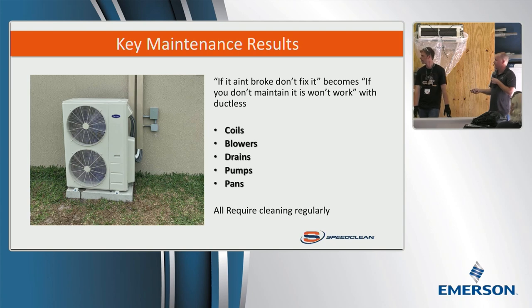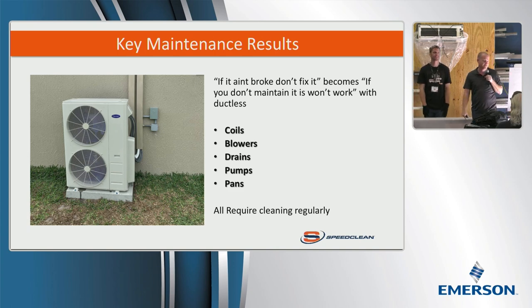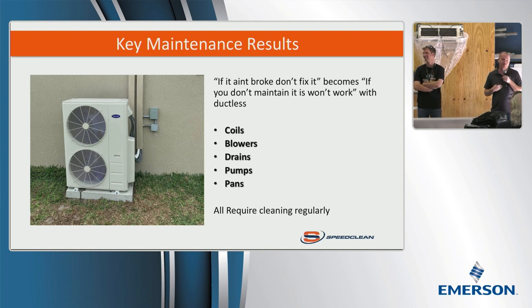Another thing I didn't mention in terms of cleaning is pumps and pans also have to be cleaned regularly. You'll get lots of problems with condensate. Have you ever seen the ductless system sitting up on the high wall with the drip coming down the wall? I had one in my master bedroom that I failed to clean the drain line in time. It's okay in your own house, you can accept it because it was your own failing. But when it's your customer's house and it's dripped on their computer or their Ming vase collection, that gets expensive pretty quick.